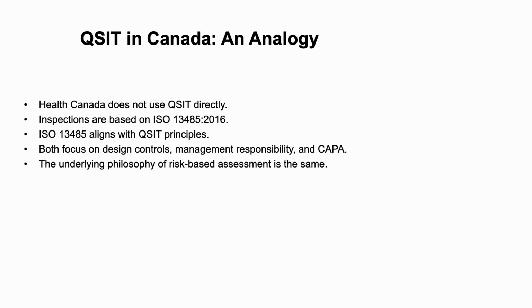While QSIT is a US FDA-specific framework, its principles have a global parallel. In Canada, for example, Health Canada does not use the QSIT methodology per se. Instead, its inspections for medical device manufacturers are based on the globally recognized standard ISO 13485:2016.